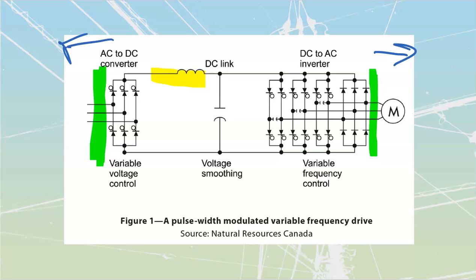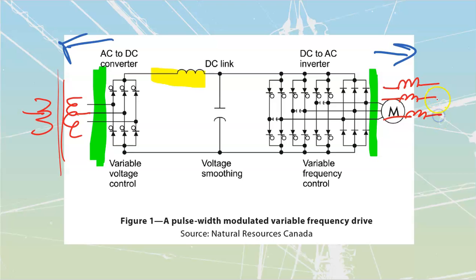On a high quality system, your VFDs, especially for a large motor, should look like this. If it's small, like 1 or 2 horsepower, you're probably not going to see much on your input. But if you're dealing with a 40 horse or something like that, you want to make sure that thing's isolated off your main lines. You do that through an isolation transformer on the incoming side, and then pass through to the other side. You'll stick reactors in line with the motor. Reactors are just inductive chokes in line that filter out a lot of our high frequencies and things like that.